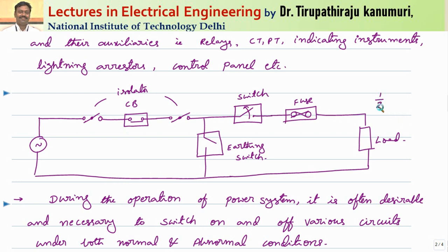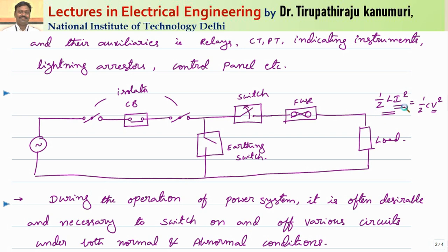Most of our loads are inductive loads. In inductive loads, the energy will be stored in the form of ½LI². So if you suddenly want to reduce this current to zero, because the inductor is an energy storage device, this energy should be dissipated to some other device. The only other energy storage element that can take this energy is the capacitor. So it has to transfer this entire energy to some capacitor in the form of ½CV², where C is the capacitance of the circuit. This energy is converted into a voltage, which rises to a huge value and will again restrike the arc and spoil your switch. So if you want to operate your switch under fault conditions, because the current is very large, the energy stored by the inductors is also very large, and when you try to break it, that creates the problem.